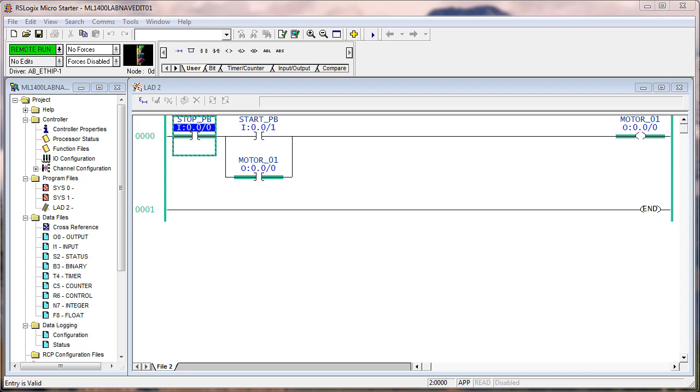If this rung goes false, in other words, if I press the stop push button, the rung is false, and over 1,000 times a second, this rung with a rung out false tells output 0/0, you're off, you're off, you're off. Sit down, sit down, sit down. Over 1,000 times a second, the false execution of the OTE tells the bit that it addresses that it's off.